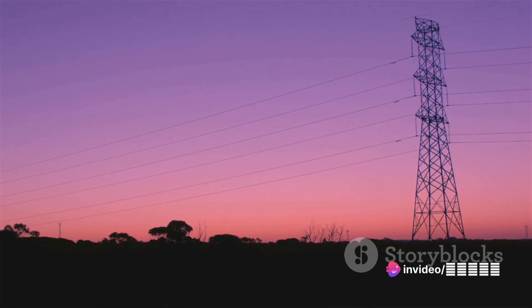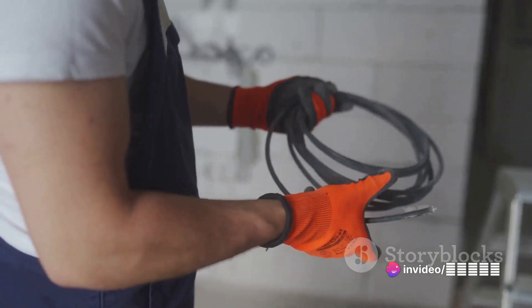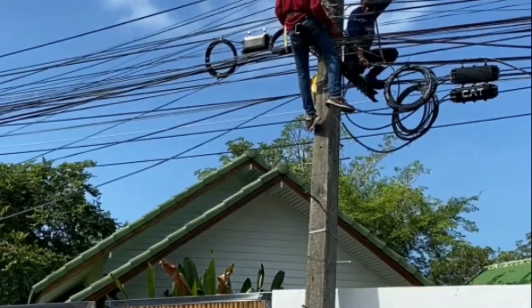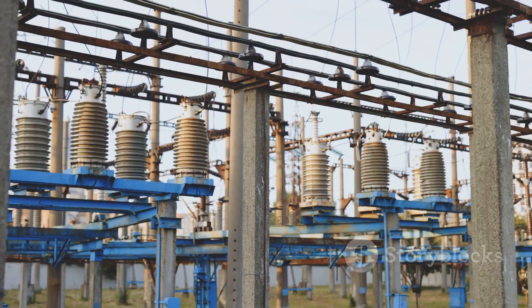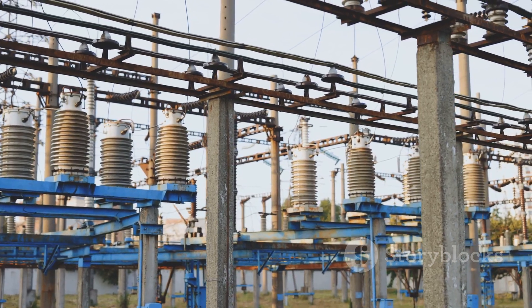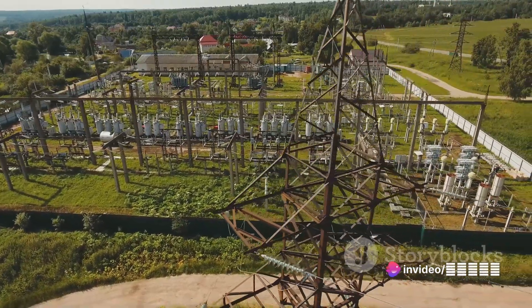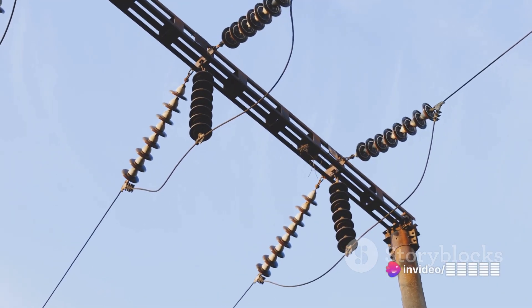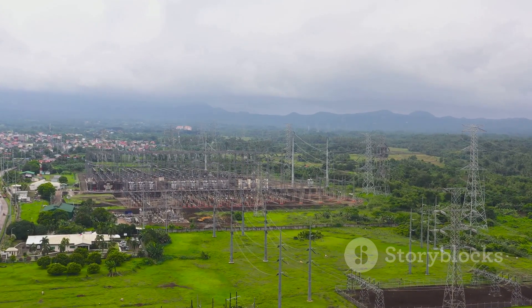These considerations are important in deciding whether to go underground or overhead when planning a power transmission project. Just as you'd choose the right tool for a job, the choice of cables for underground transmission is crucial. First up, we have high-pressure fluid-filled cables, often used for long-distance high-voltage transmission. The fluid serves a dual purpose: it insulates the conductor and helps dissipate heat, allowing for efficient transmission. Next, solid dielectric cables are typically used for medium to high voltage transmission, made from solid materials like polyethylene or rubber. They are resistant to environmental factors such as moisture and temperature, making them a reliable choice.